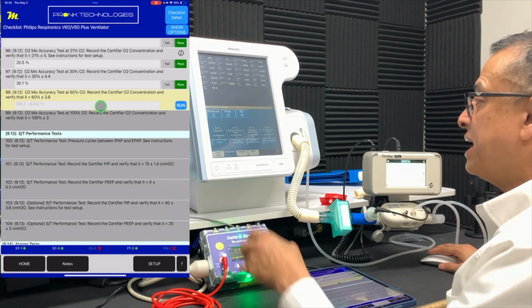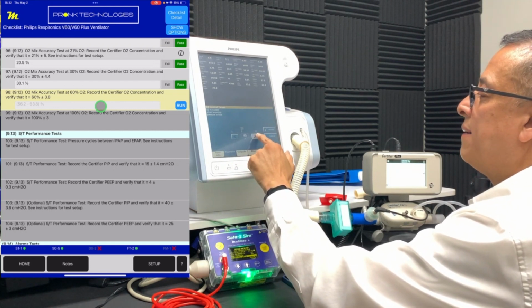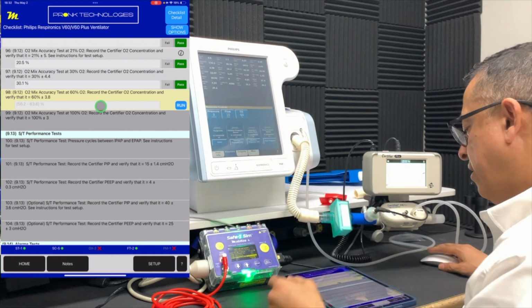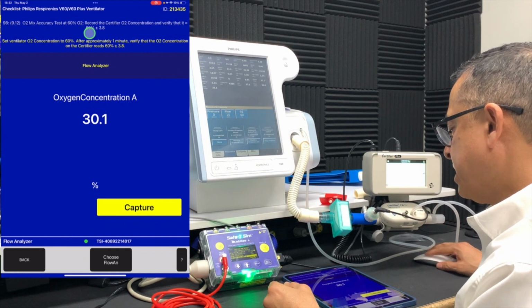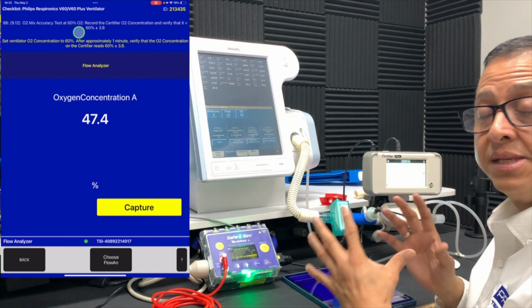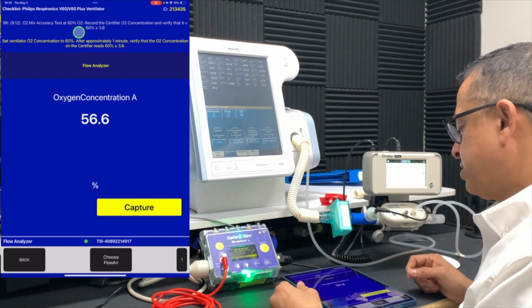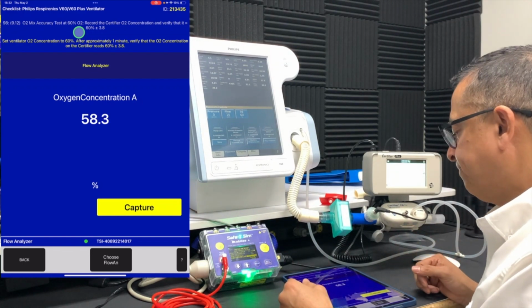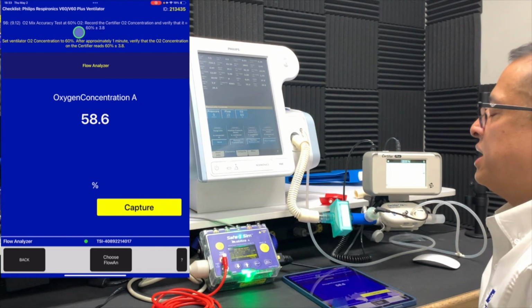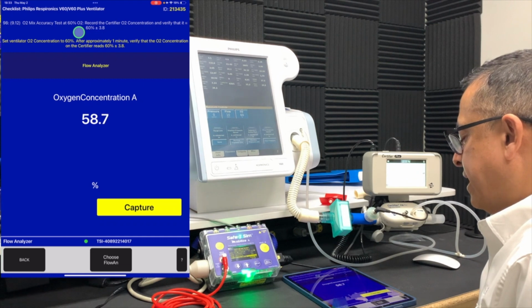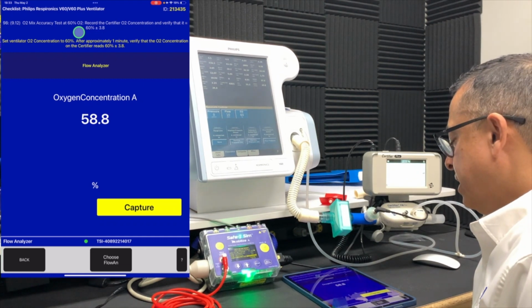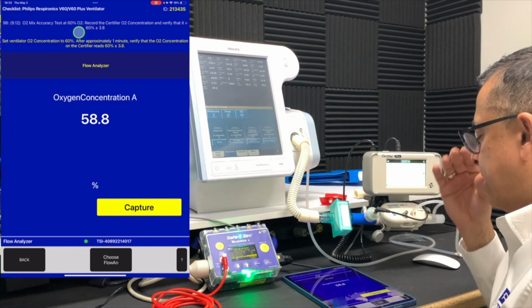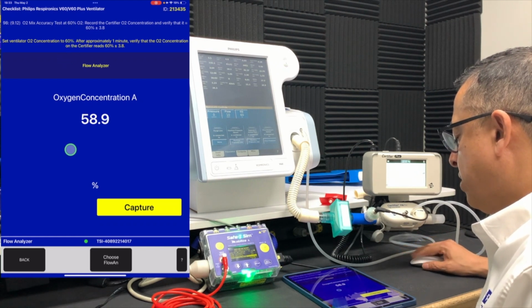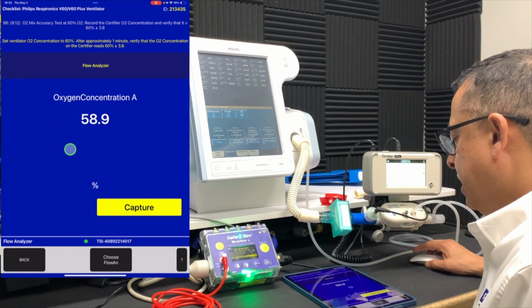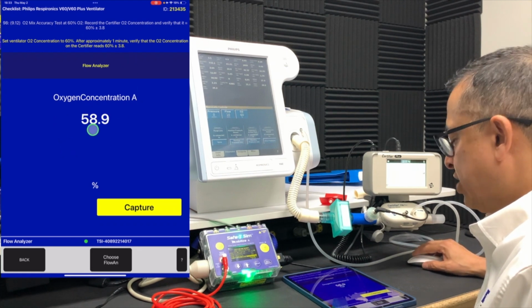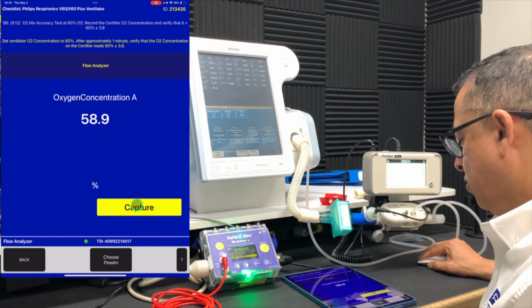And we want to again now do it at 60%. So now we'll increase it to 60% and do the same thing. So you always want to make sure you follow the instructions, run the test. You have your tolerances and your test point listed. Here's another reference. As we're doing a lot of these tests, it's easy to think that we remember or recall all of the values. So it's really helpful to have the procedure there in front of us, guiding us all the way through. So we can see here as the oxygen concentration is flowing, it's increasing. We'll wait for the measurement to stabilize, to also confirm that the value does not fall out of tolerance as required by the manufacturer. So we'll give it another moment or so to make sure that that oxygen concentration value is stable. And you can see here we're right at almost 59, still within tolerance. It's holding stable, not dropping or varying in any way. So feel confident it's working properly. We can capture that result.